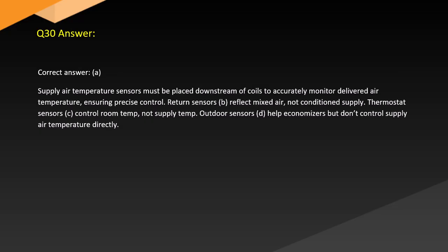Answer. Correct answer. A. Supply air temperature sensors must be placed downstream of coils to accurately monitor delivered air temperature, ensuring precise control. Return sensors, B, reflect mixed air, not conditioned supply. Thermostat sensors, C, control room temp, not supply temp. Outdoor sensors, D, help economizers but don't control supply air temperature directly.